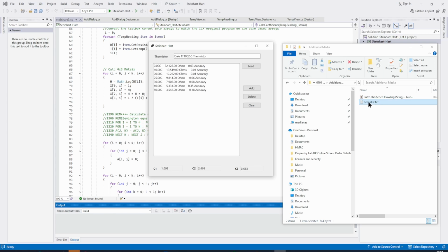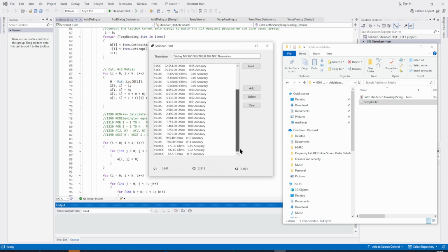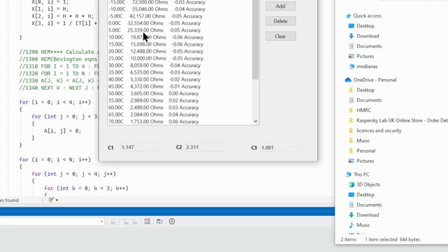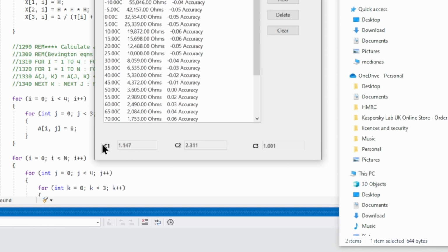So I've got this file, it's called templist.txt. I can take this and drop it on my computer program. It tells me what I'm importing, and then it imports it. And so here we go, -40, the resistance that it finds there, and it's worked out a curve with coefficients at the bottom. So C1, C2, C3 coefficients, and what it's done then is what the actual unit will do and converted them back and tried to work out, if I receive that number of ohms and I apply these coefficients, how far off the true reading will I be? Well, here's 25 degrees centigrade, and the answer is I will be 0.05 degrees below the optimal reading.